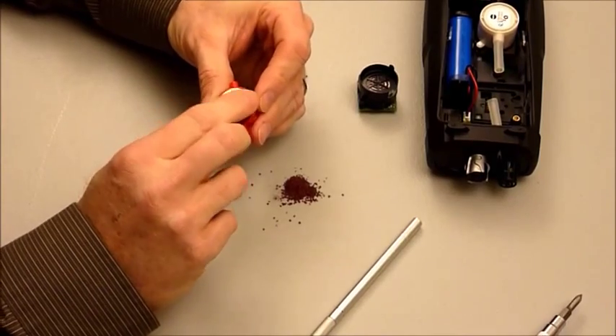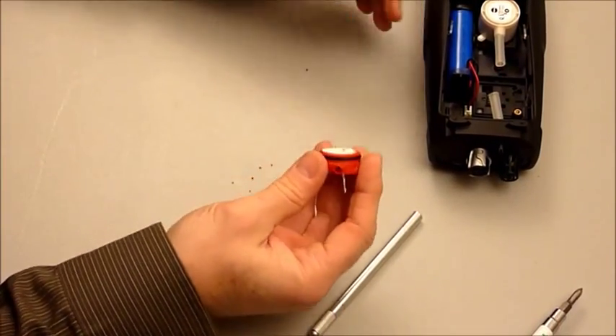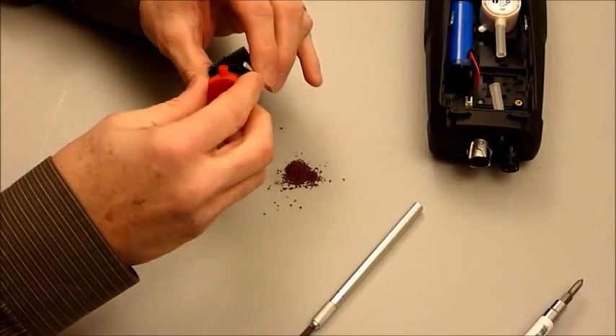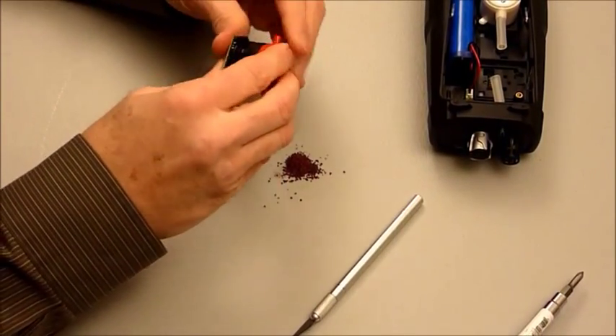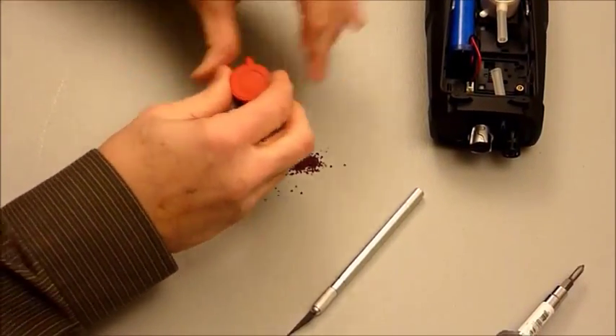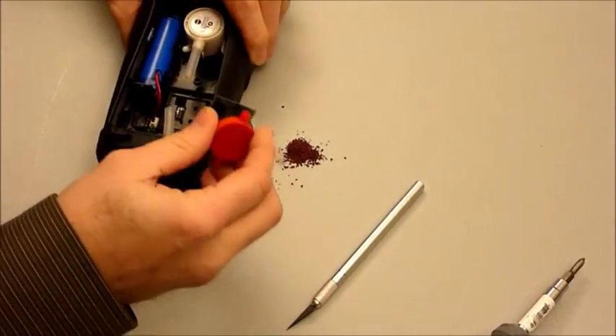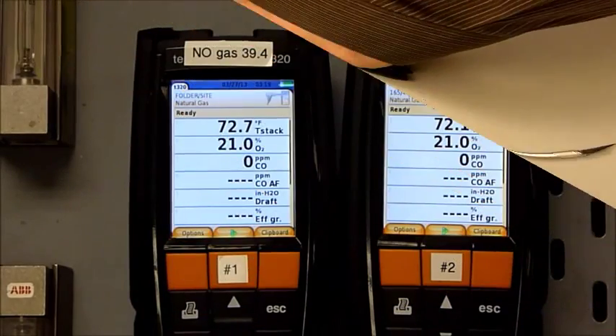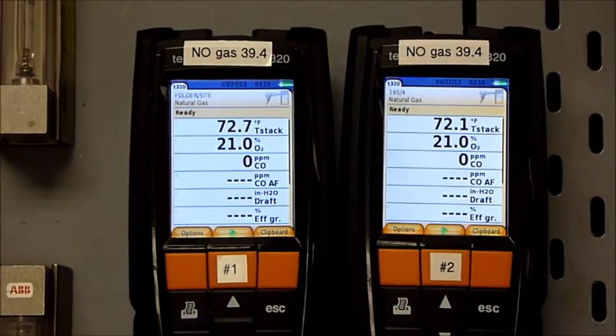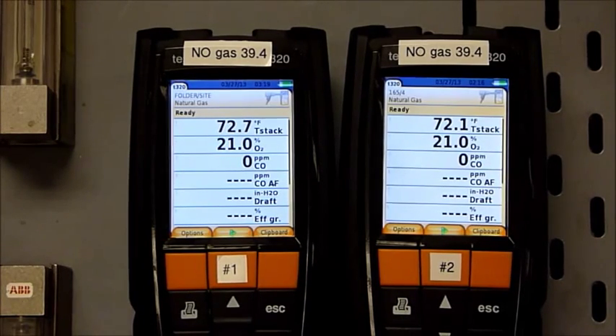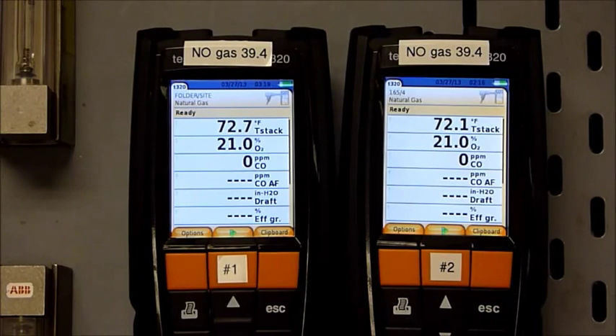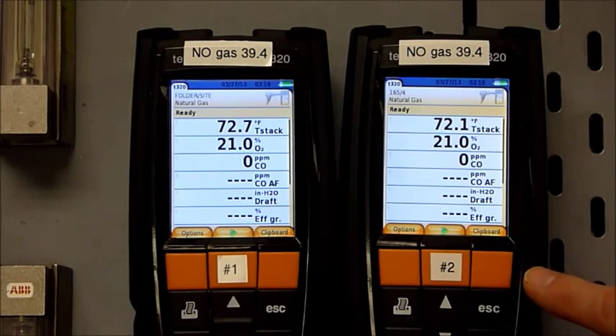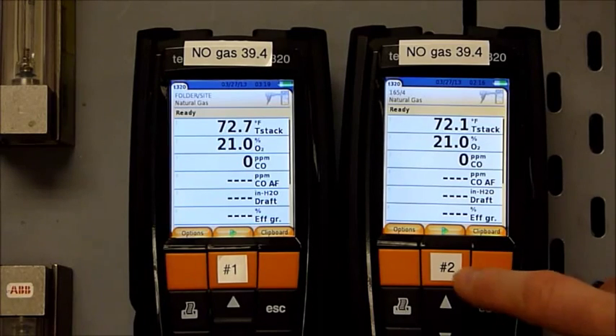Many flue gas analyzers use sensors that don't include this material. Now we're back at the calibration lab, and we're running the same analyzers on the nitric oxide calibration gas at 39.4 ppm. The only difference is that analyzer number two has got a CO sensor with the NOx filter removed.